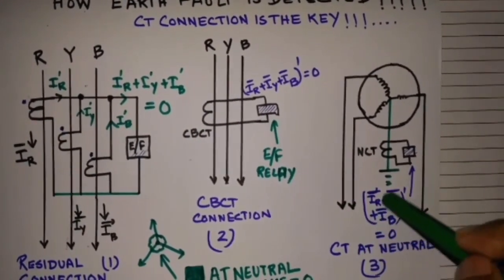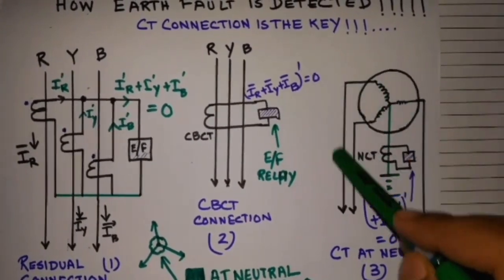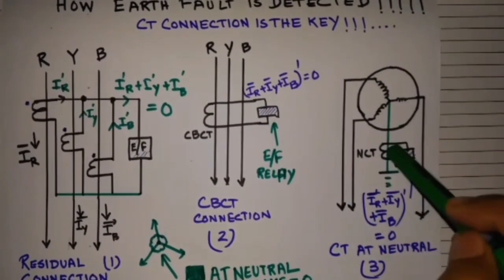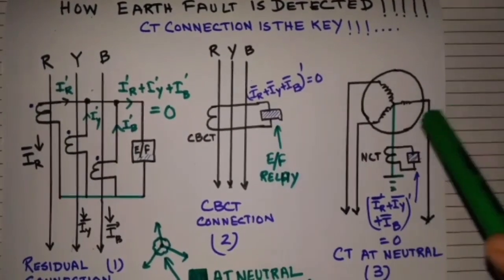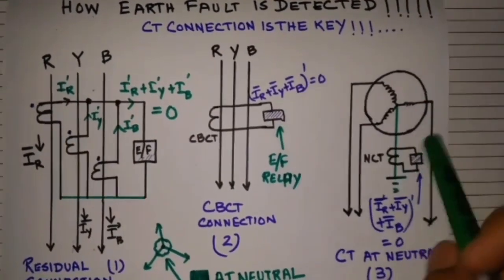But when there is an earth fault, suppose this phase has faulted, so it will return to this path. The current path will be like this. Then this CT will see a current value and will cause the relay to energize.